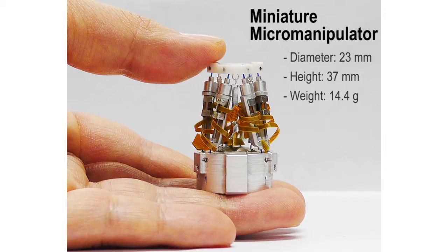As a result, the manipulator provides six-degree-of-freedom motion of the end effector within a cylindrical workspace four millimeters long and four millimeters in diameter, while allowing for a remote center of motion at the point of entry through the sclera.